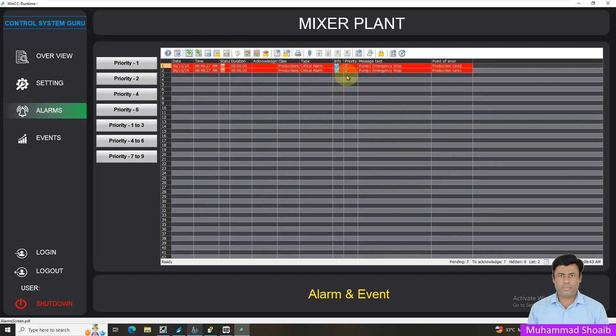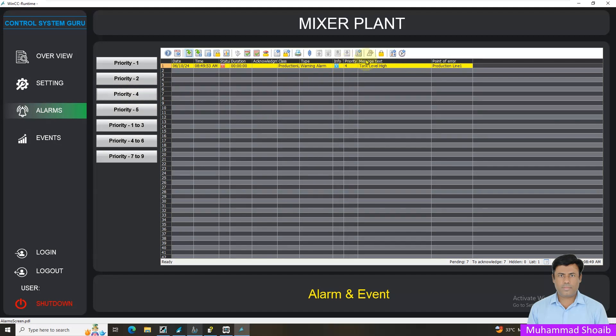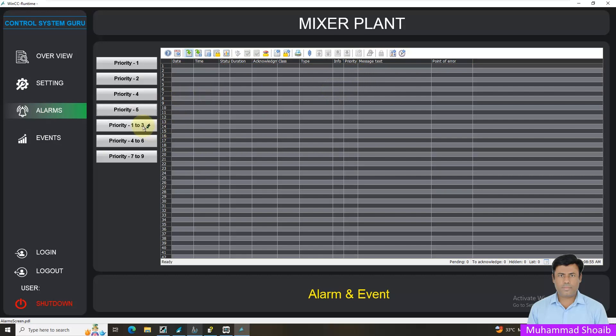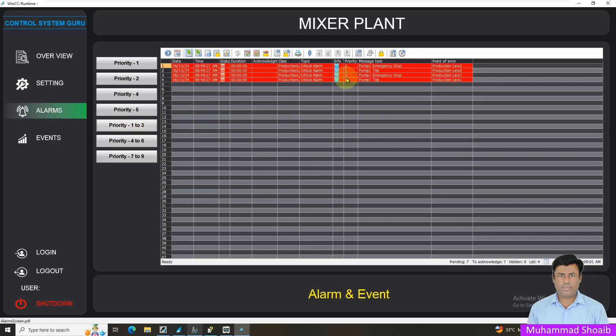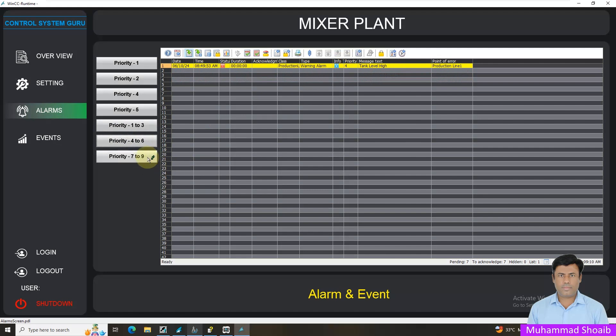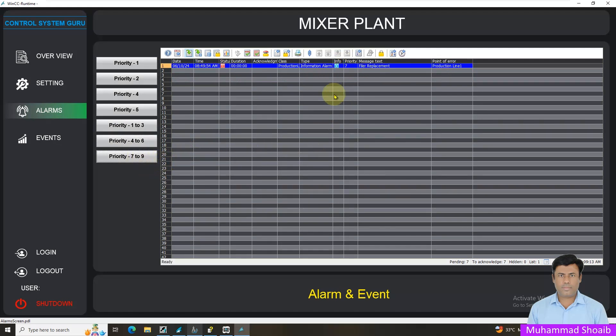And if I filter priority two, as you can see the priority two alarms come up — four alarms. Similarly, pressing five shows nothing because I don't have any priority five alarms. If I want to filter between priority one to three, we can filter alarms between priority one, two, and three. Similarly, between four to six and seven to nine we can also filter. Let's see practically how we can configure alarm priorities and filter by priority.